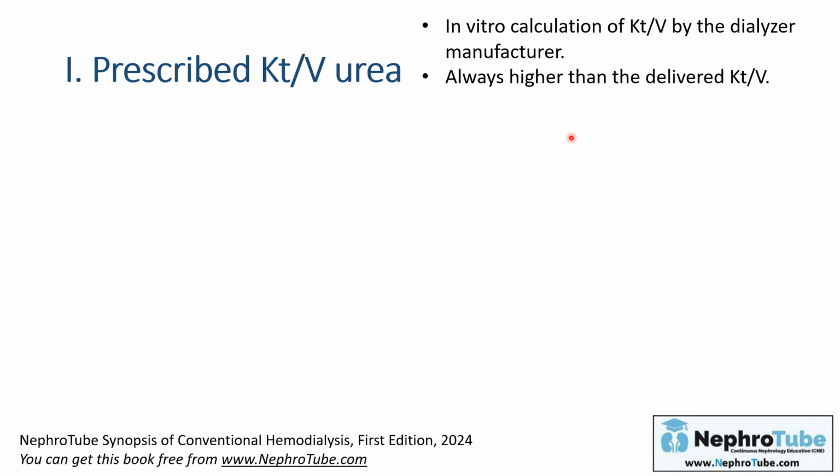For example, before we mentioned that the dialyzer clearance that is mentioned by the manufacturer in vitro was always higher than the actual dialyzer clearance inside the patient's body. We mentioned that in the lecture of the dialyzers.